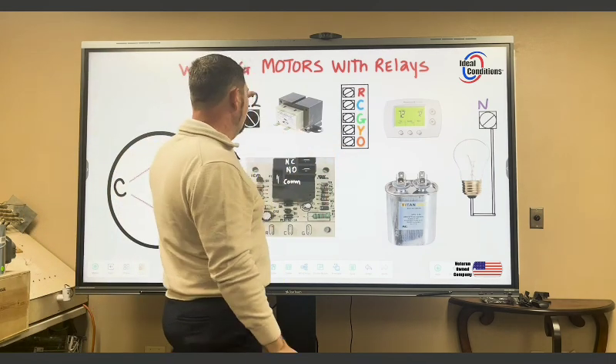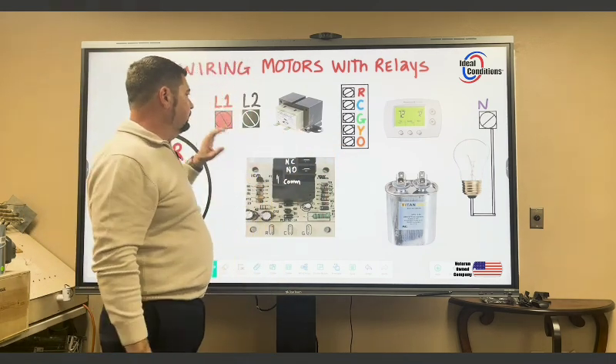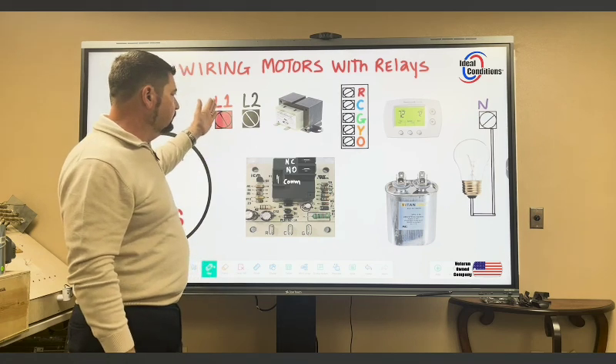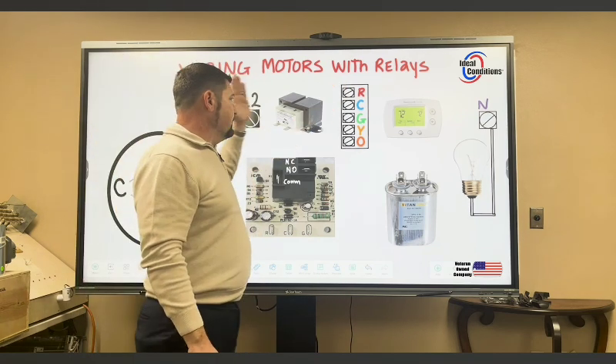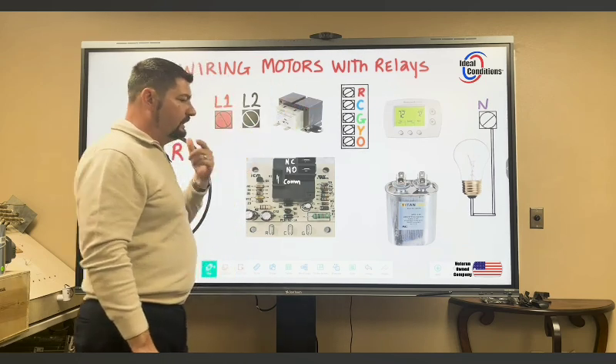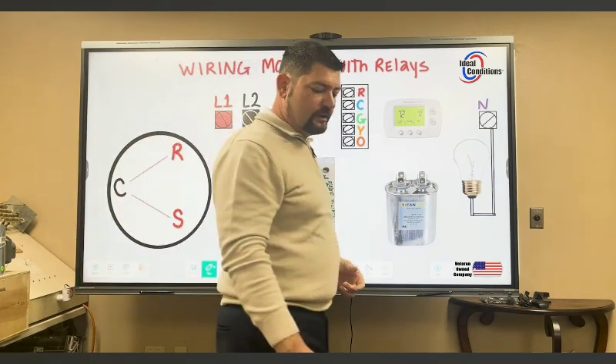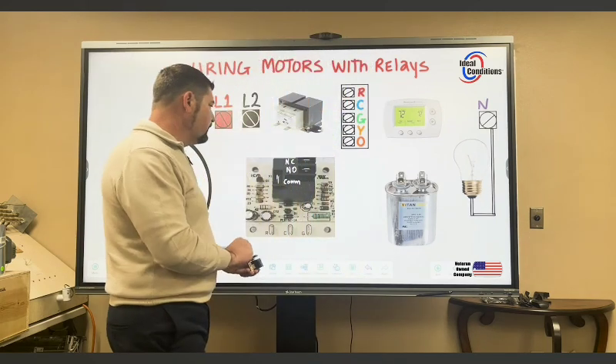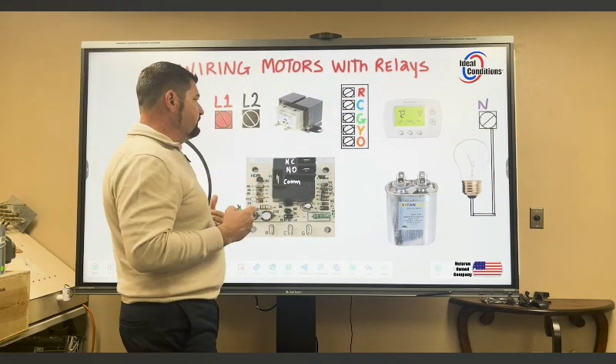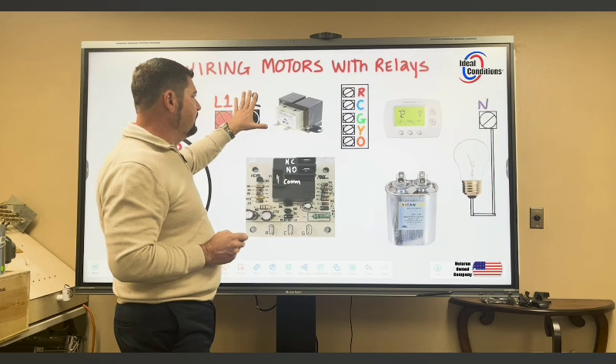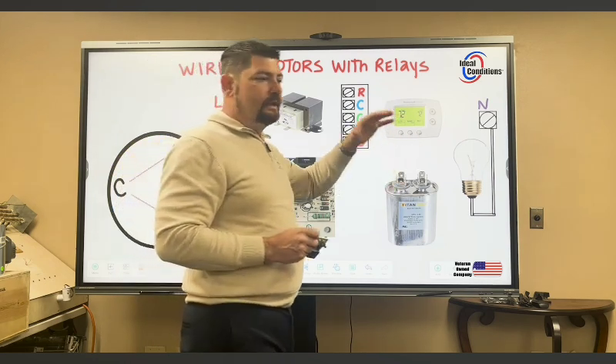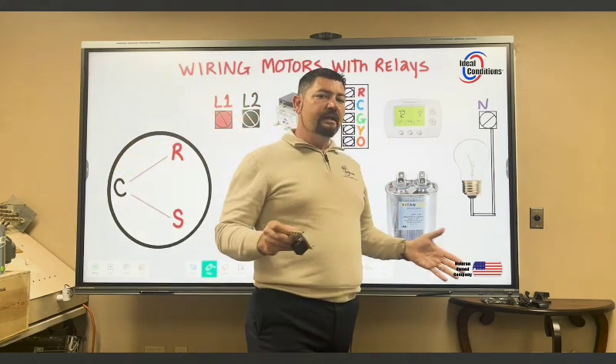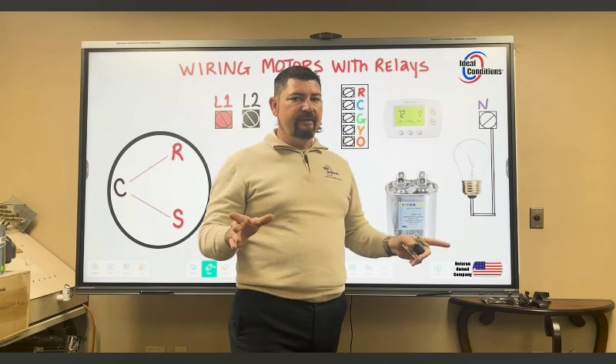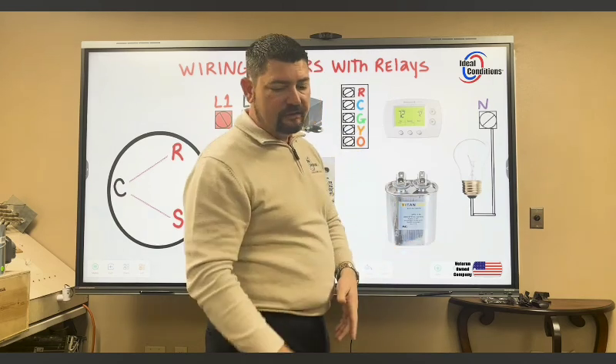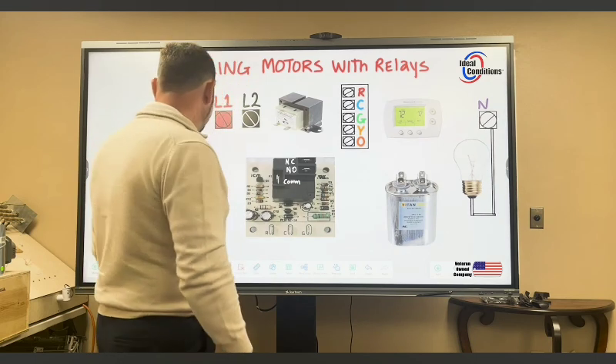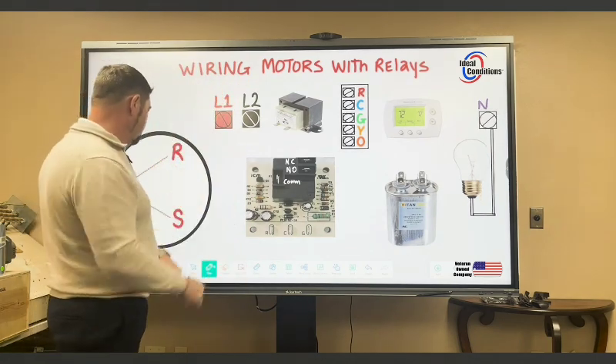Is it going to L1 or L2? Because the last thing you want to do is take something that's colored red and just start wiring things together, because then if you cross those paths, you're going to hurt yourself and you're going to cause harm to the equipment. So keeping that in consideration, it's better practice to actually take one leg of power, wire it up to all your devices, and then when you can inspect that and verify that path is correct, then you can work on that next step, that next leg of power. So we're going to go ahead and do that here.